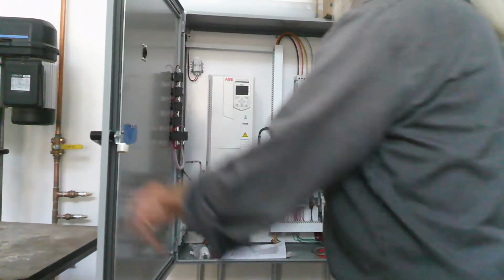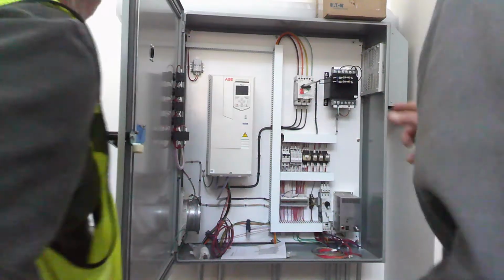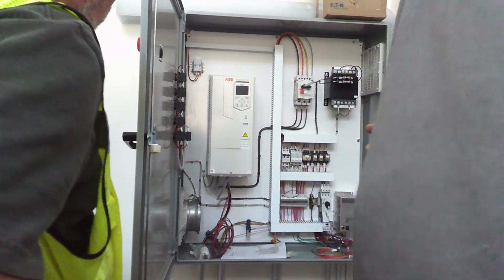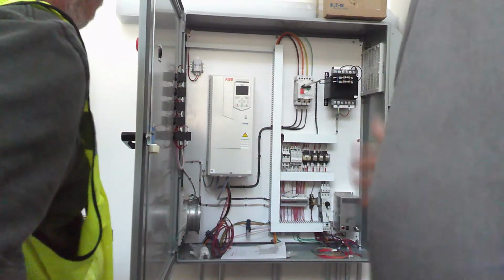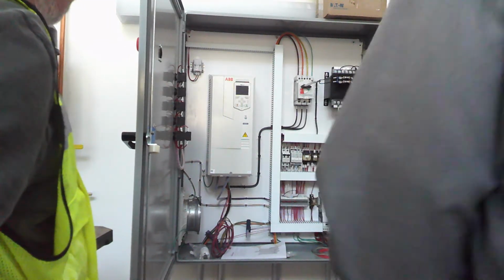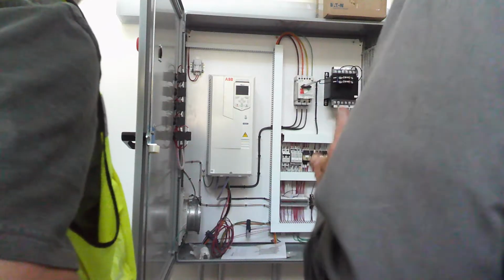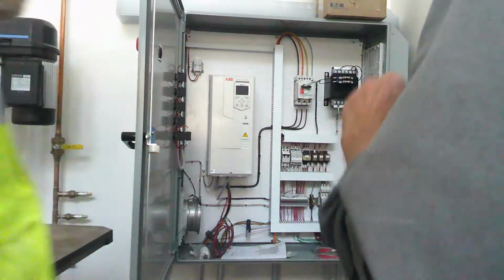This is a constant volume system, and if we look in here, you see the VFD. The VFD is for balancing only. Once it's set up, it just stays that way, because this is a direct drive system, so there's no belts, no pulleys to adjust. And the airflow on this thing is critical.